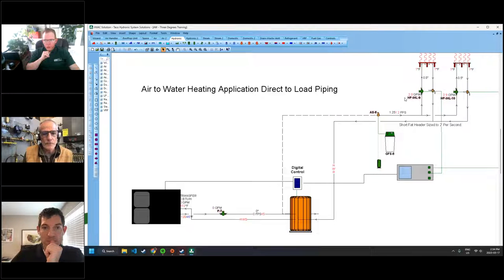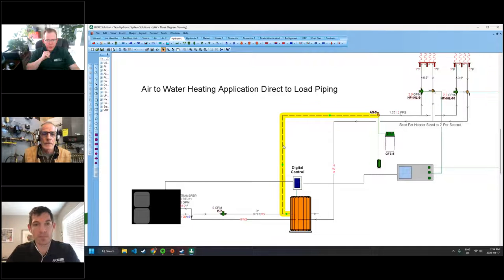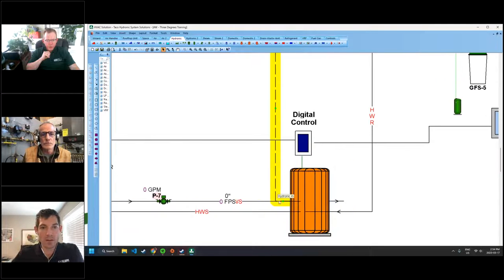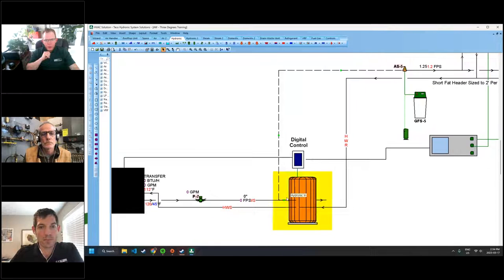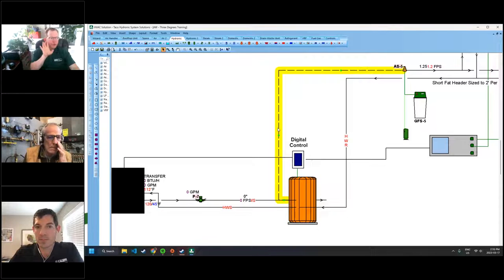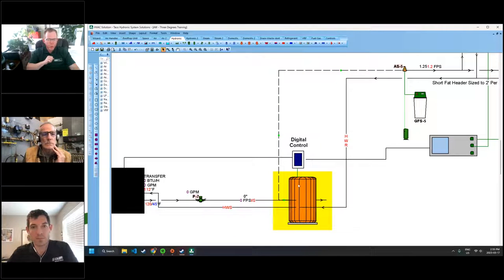For sure. And the other thing that you can do is, right now you can see these are both matched loads of 2.9. But if we put zone valves on this, and let's say this is only pulling half a gallon a minute, this direct to load still works, because if we make sure that this piping right here coming off of the actual buffer tank is amply sized, whatever needs to be drawn off here will naturally draw off, and the remainder will end up going into that buffer tank, and it will serve its purpose of decoupling the two systems.